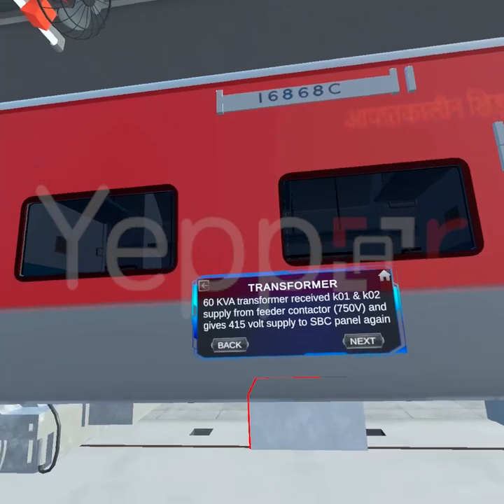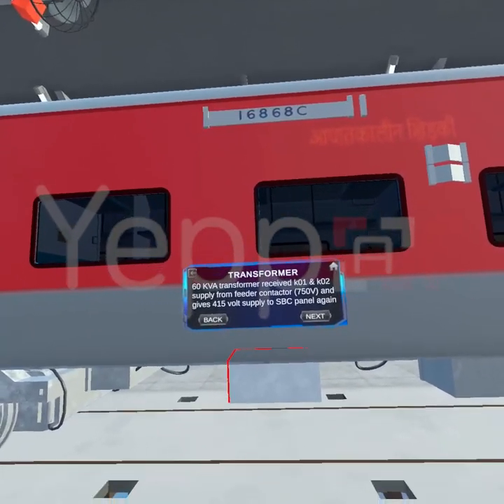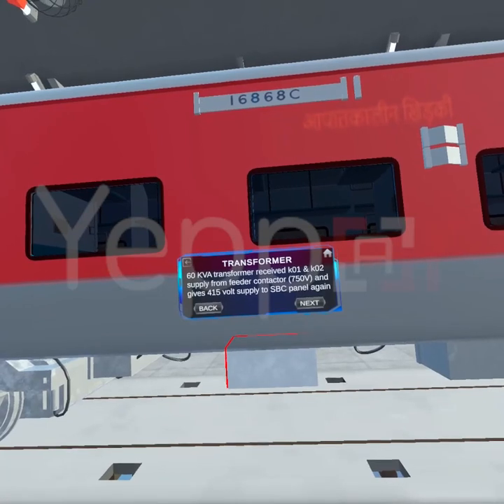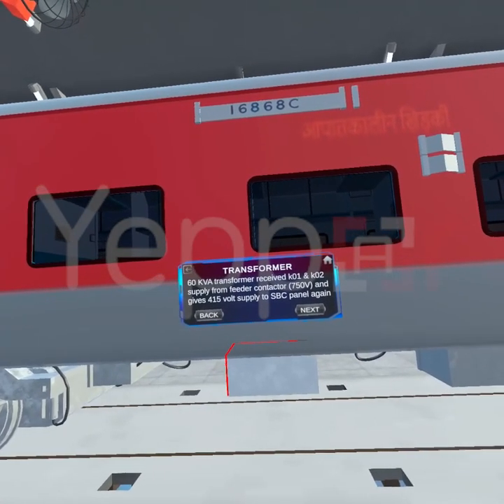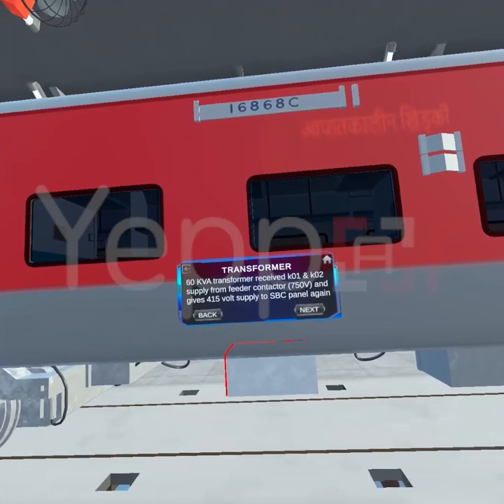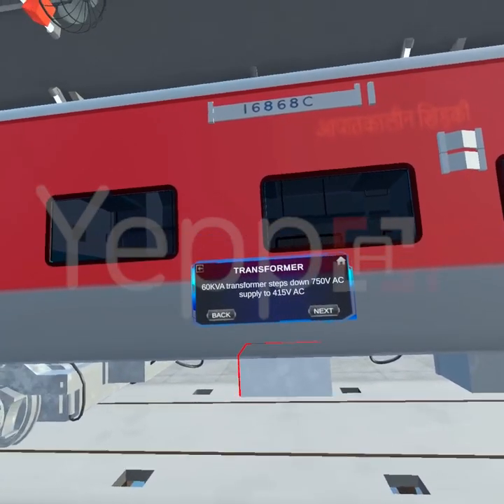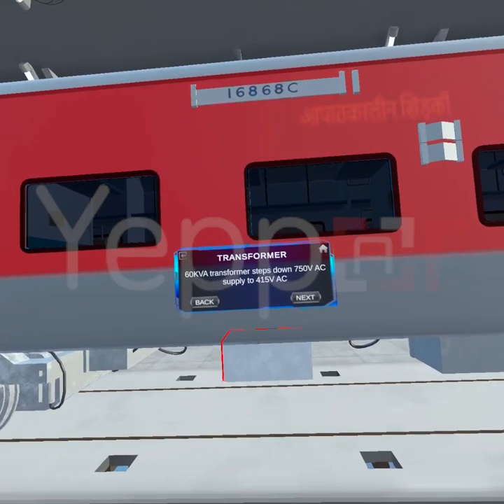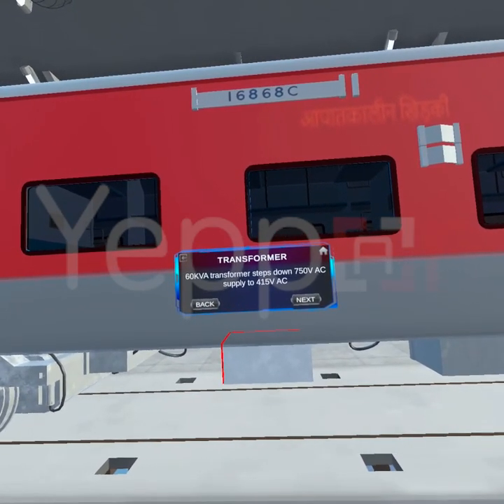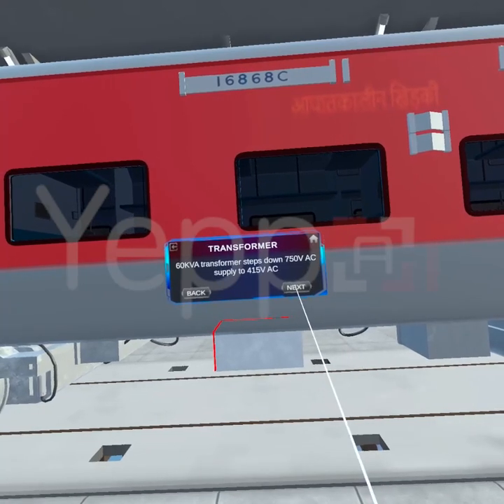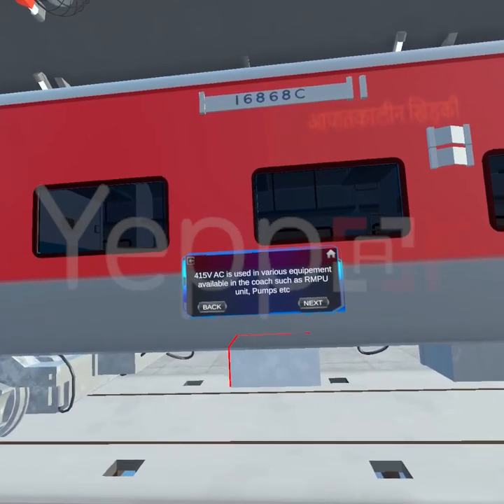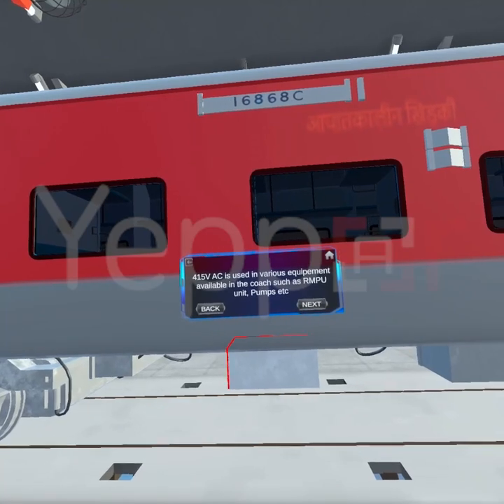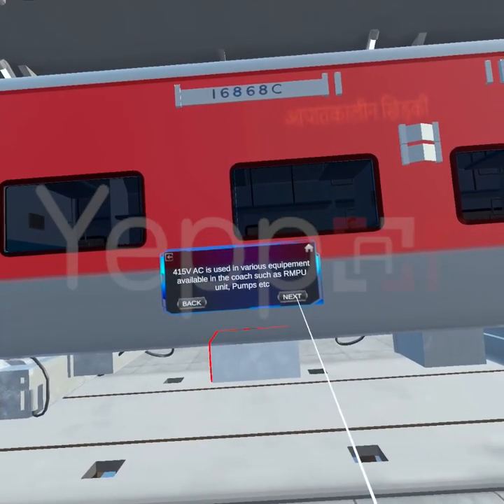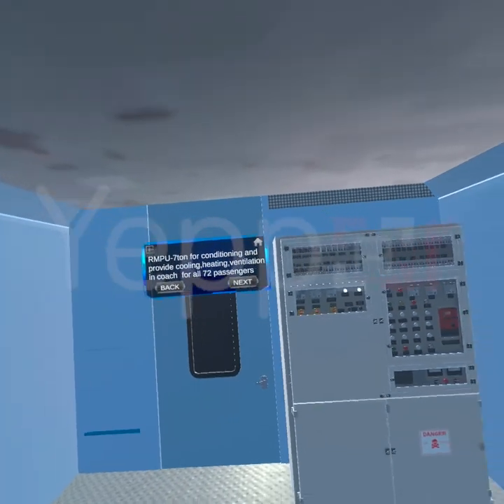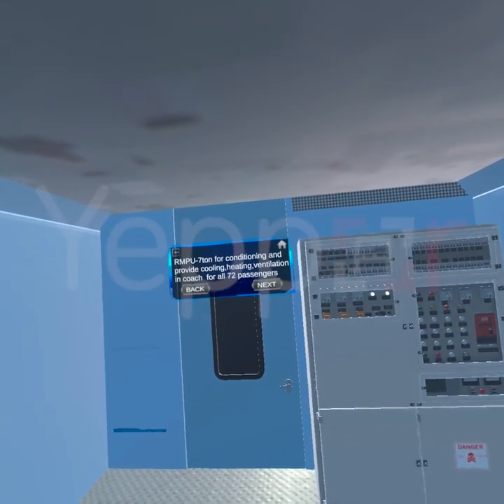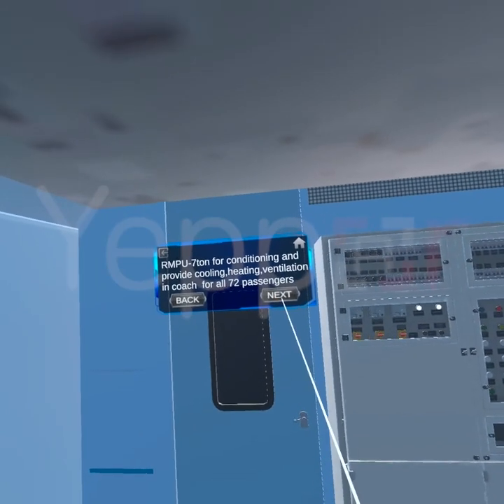60 kVA transformer receives K01 K02 supply from feeder contactor, 750V, and gives 415 volt supply to SBC panel again. 60 kVA transformer steps down 750V AC supply to 415 VAC. 415 VAC is used in various equipment available in the coach such as RMPU unit, pumps etc. RMPU, 7-ton, is for air conditioning and provides cooling, heating, ventilation in coach for all 72 passengers.